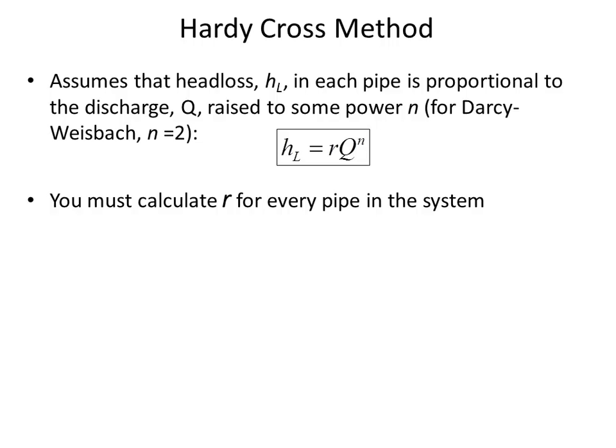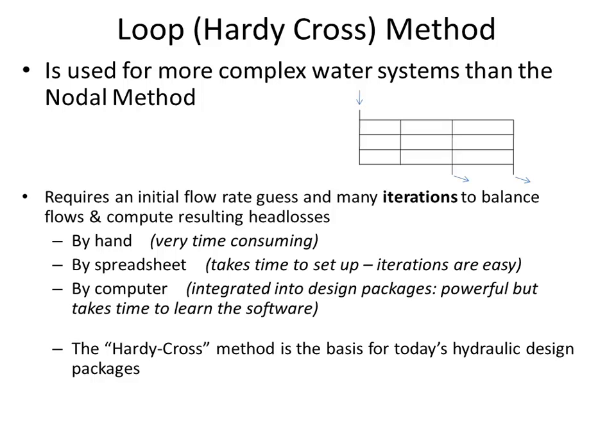So the first thing you do when you're trying to solve this is you say, all right, I've got a certain pipe here. What's the R value for it? For this pipe length that is given to me, the diameter of the pipe, using my first guess of what the f value might be, the cross-sectional area, all those parameters that go into R, what's the resistance through that pipe? And the higher the R value, the more resistance there is to flow through the pipe, and that gives you a relative idea of what the flow rates might be.